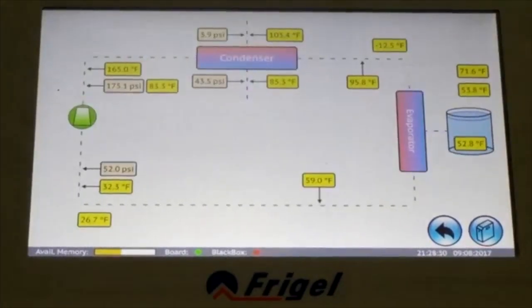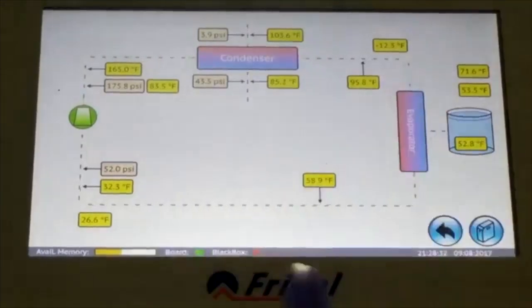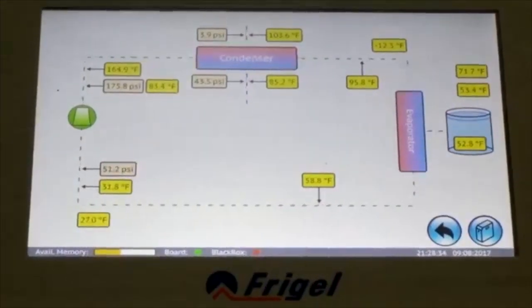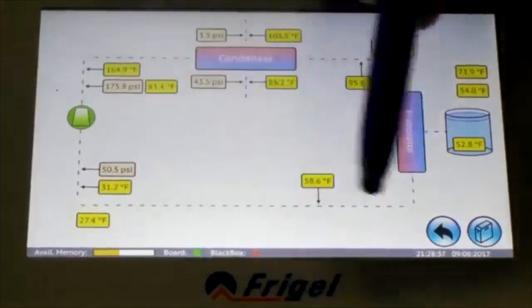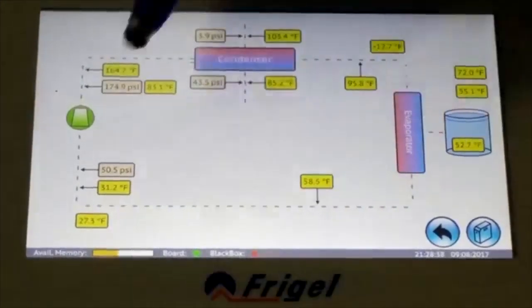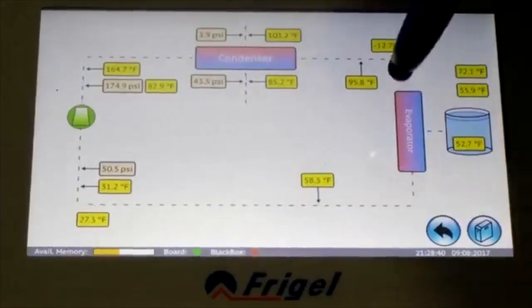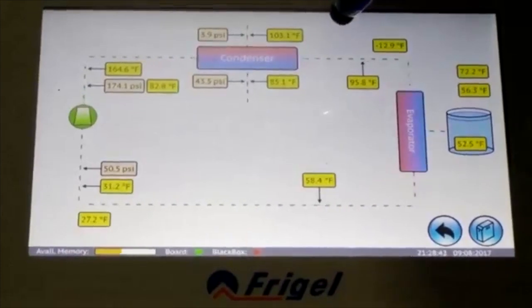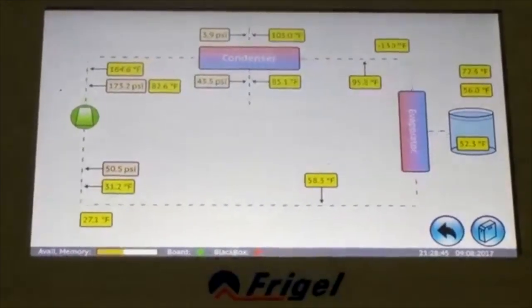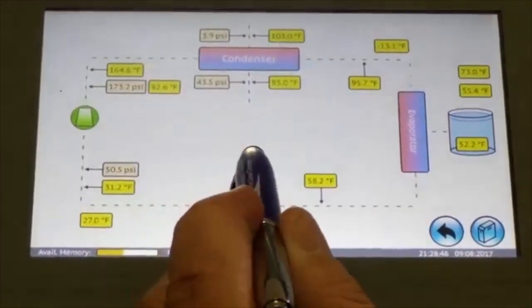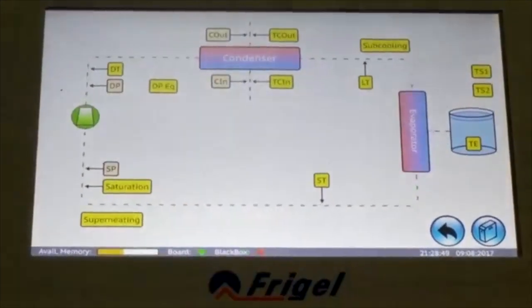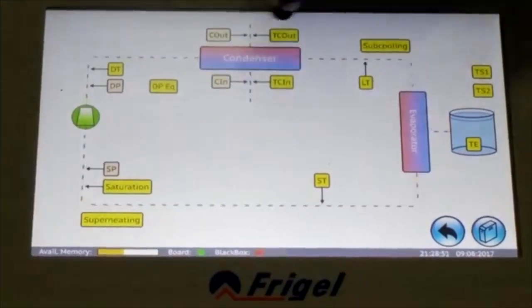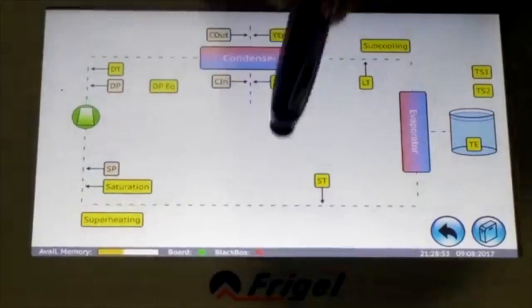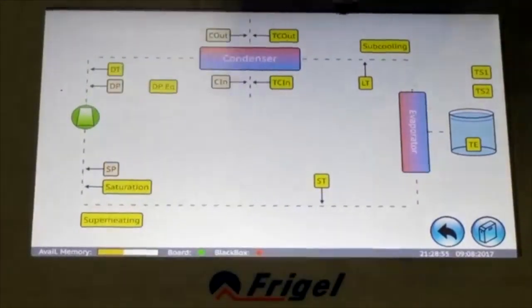On the next screen, all refrigeration parameters are indicated graphically. All refrigerant temperatures and pressures are displayed. This is particularly useful for service technicians. Pressing and holding anywhere on the screen and the parameters are given to correspond to the unit operating schematic, including saturation, subcooling, and superheat factors.